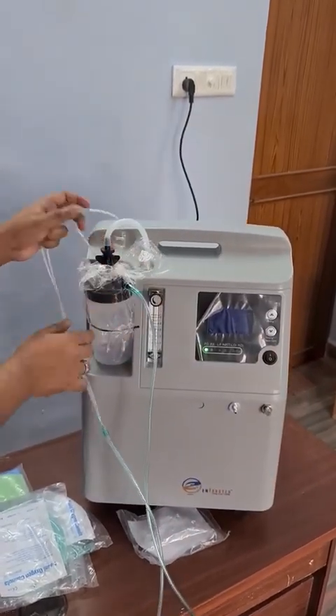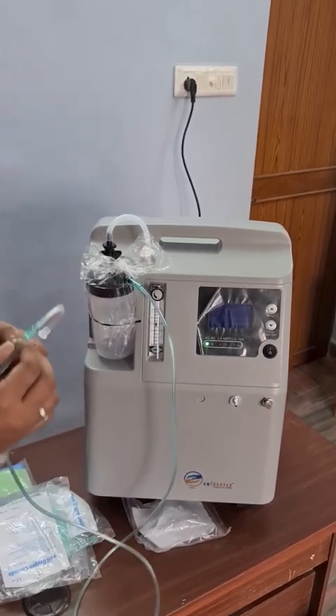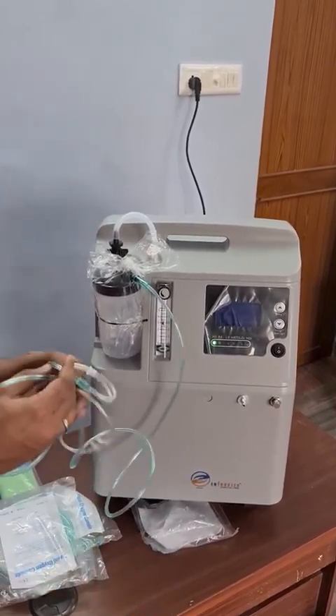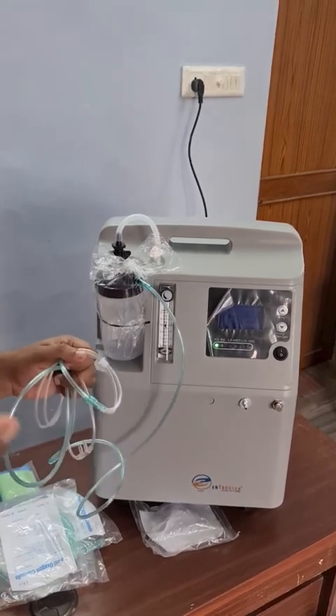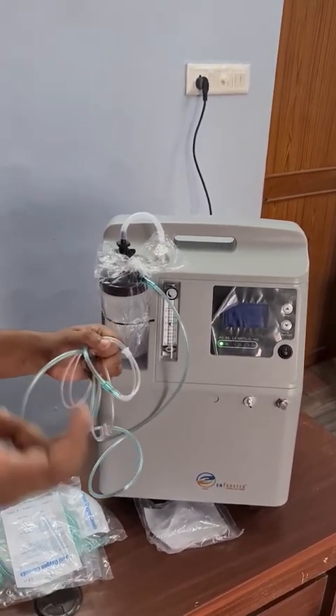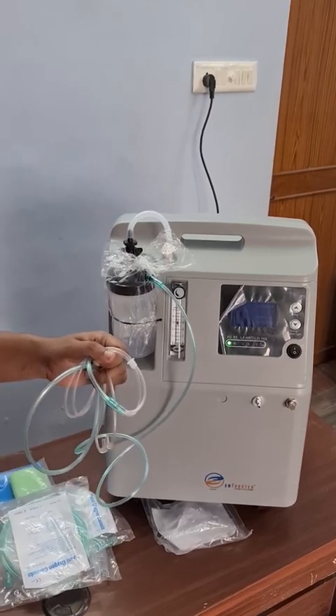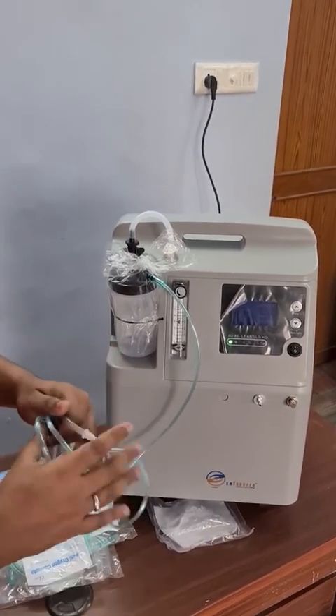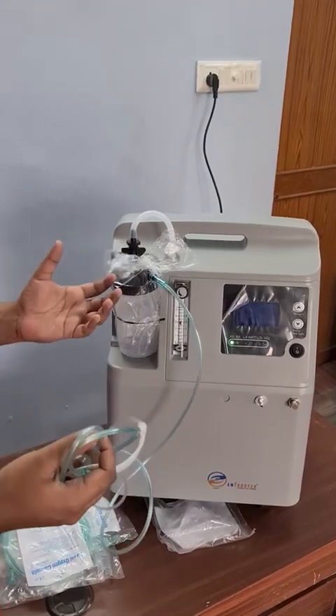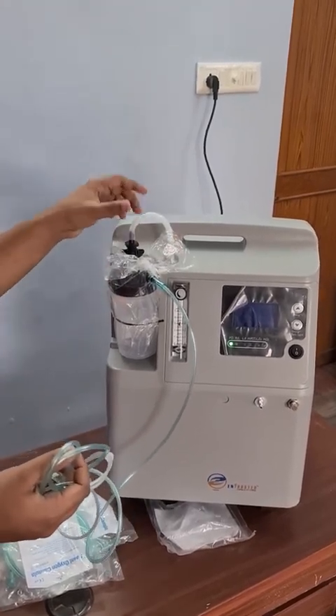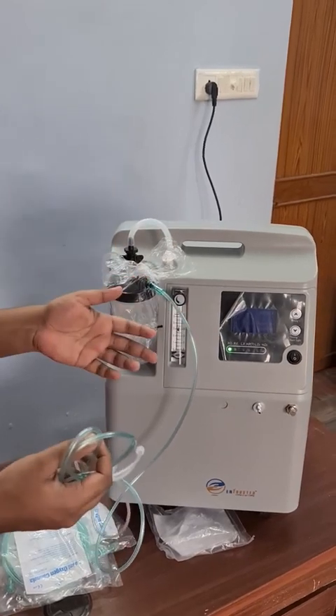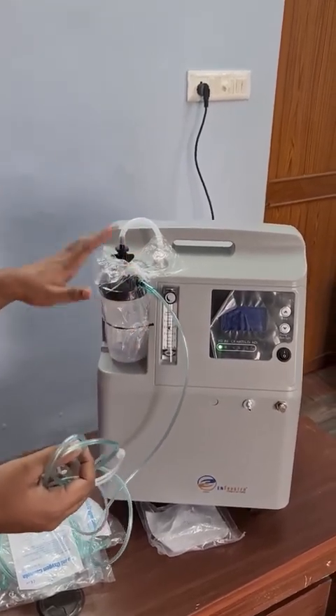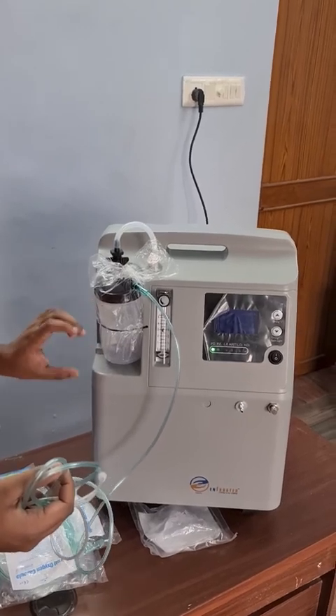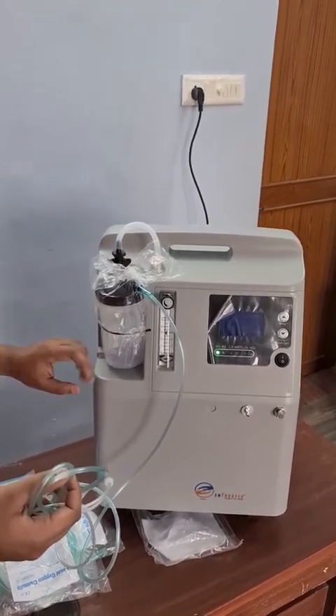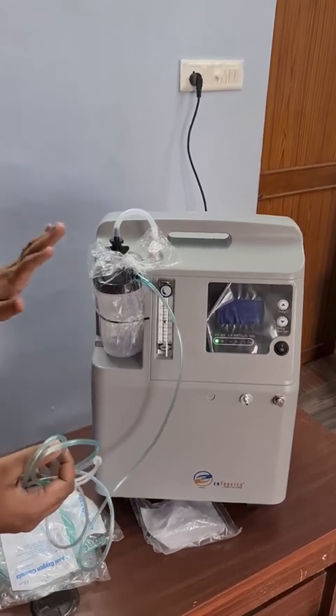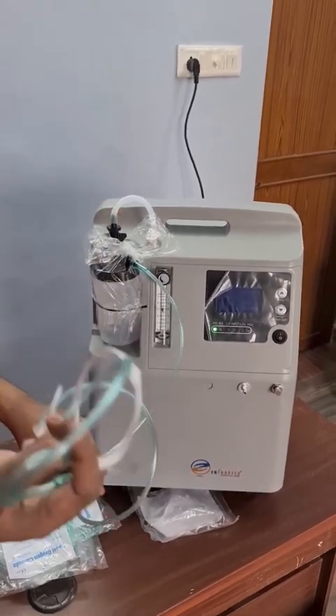Now, adding water. As I told you, the water needs to be purified water or distilled water. You cannot add salt water, and there is no need to boil the water before adding it. Just add purified water, which is free from salt. If you add salt water or water with salt content, these ports will get clogged and back pressure will build up on the device, thereby breaking the compressor. So always add only purified water, RO water, or if possible distilled water. That is the best. That's how we use the concentrator.